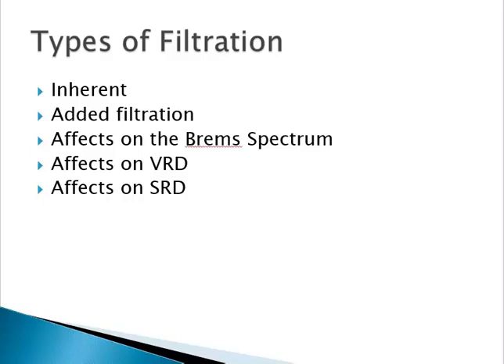Filtration: we have two types — inherent filtration and added filtration. Different textbooks give different definitions. By the strictest definition, inherent filtration is only the glass that holds the vacuum in the x-ray tube. You could theoretically hook up electricity to an x-ray tube with no housing and make x-rays — they did that in the early years of x-ray creation. So that glass truly is your only inherent filtration, but you can't legally expose somebody to that x-ray beam.